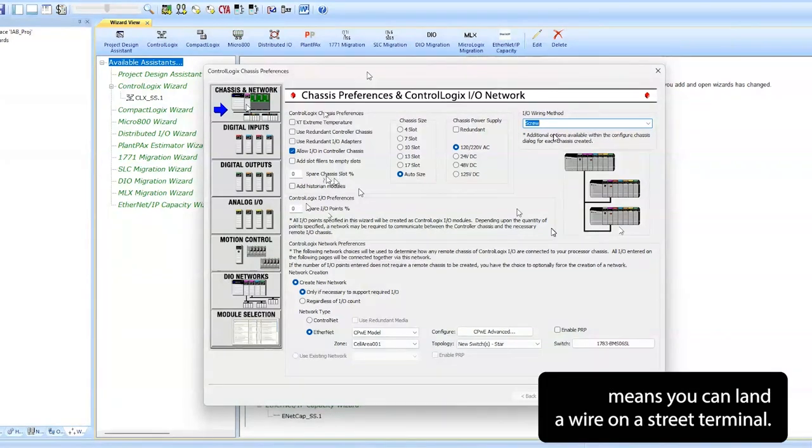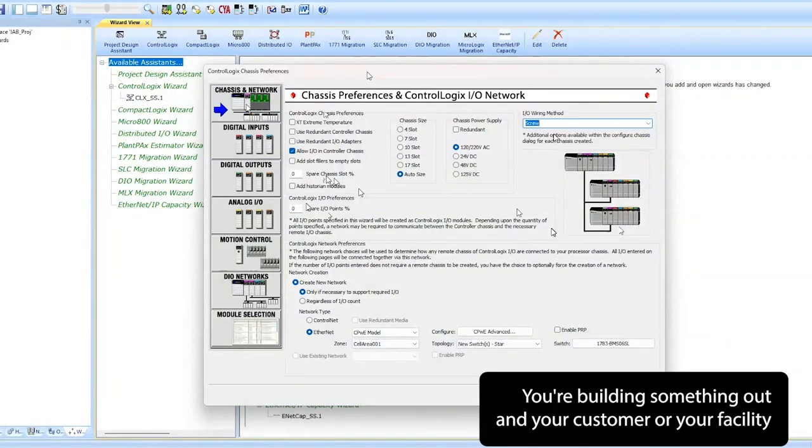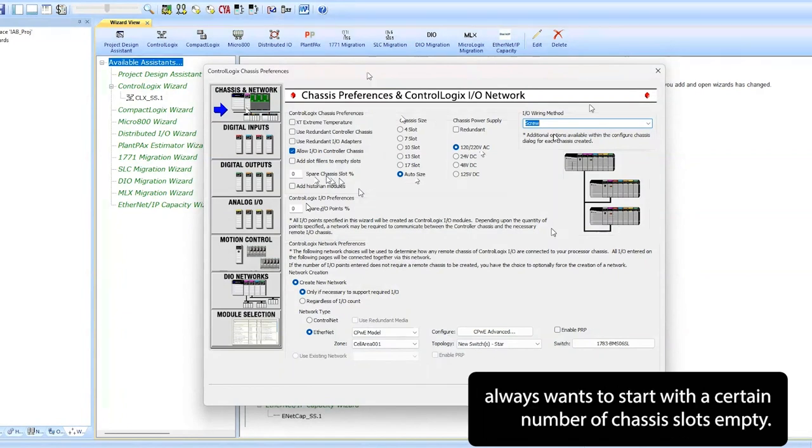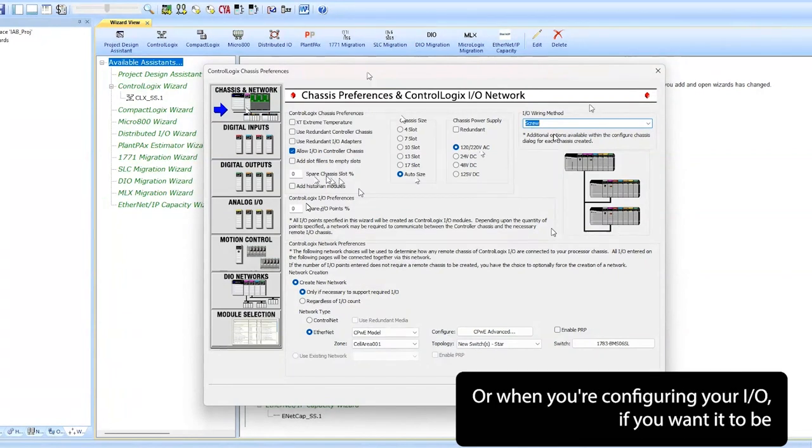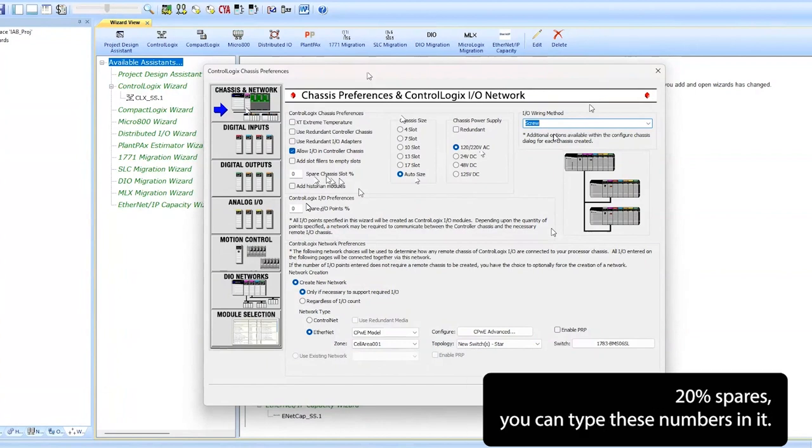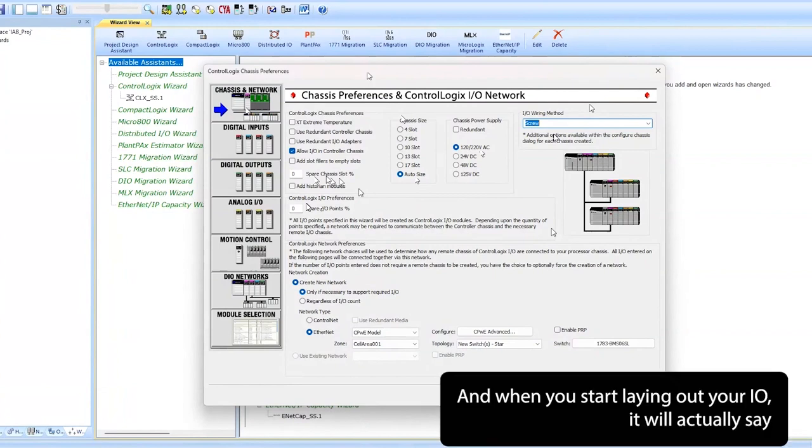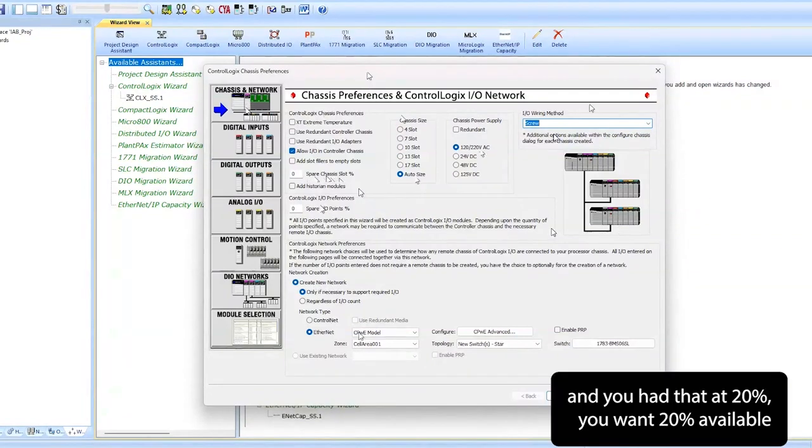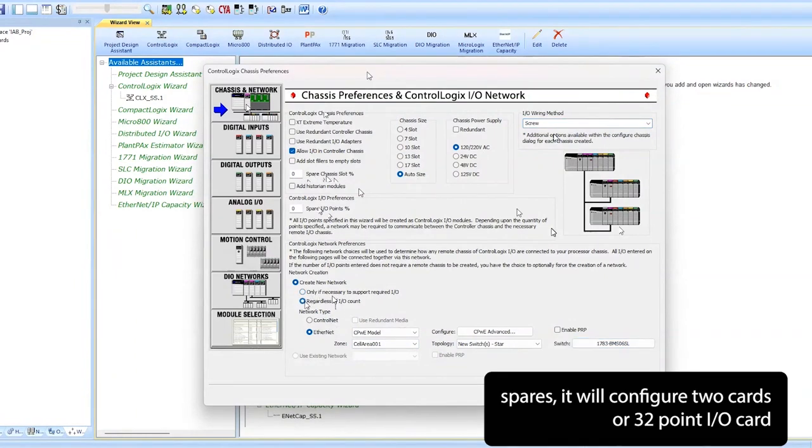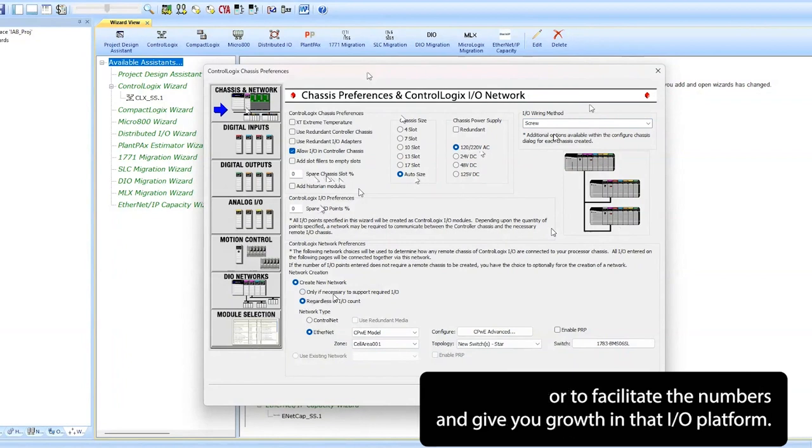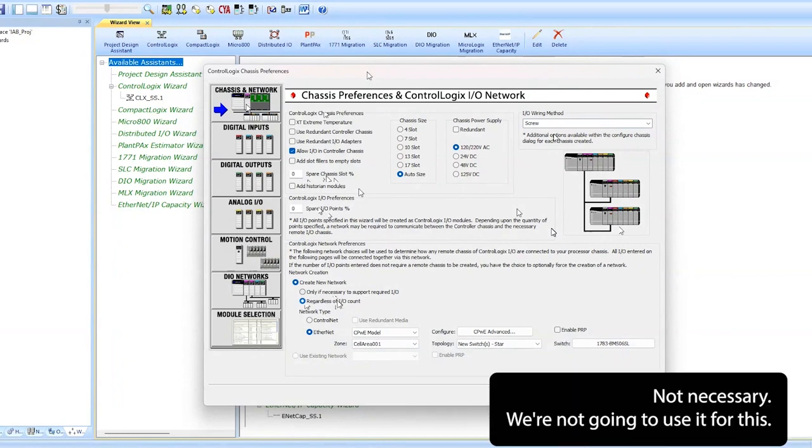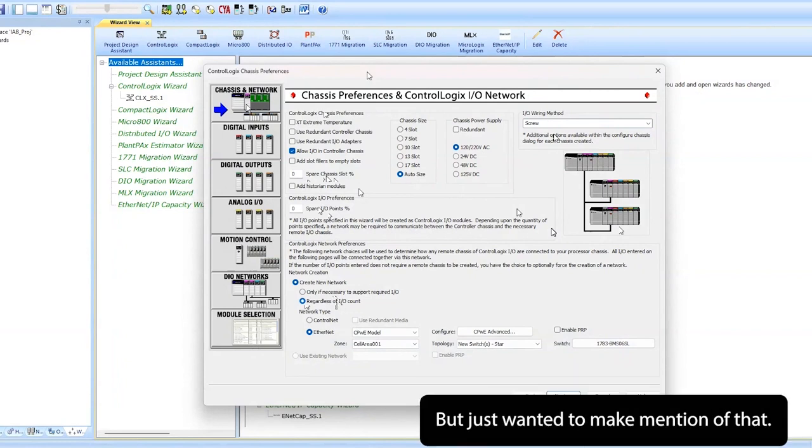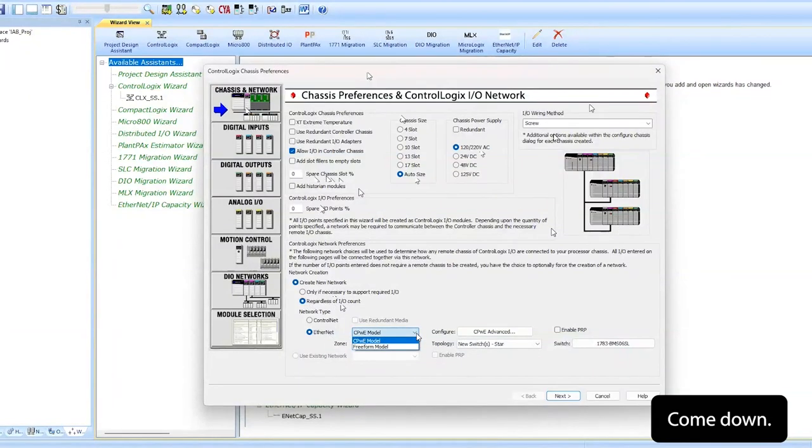If you're building something out and your customer or your facility always wants to start with a certain number of chassis slots empty, or when you're configuring your I/O, if you want it to be 20% spares, you can type these numbers in. When you start laying out your I/O, it will actually say if you needed 17 inputs and you had that at 20% spares, it will configure two cards or a 32-point I/O card to facilitate the numbers and give you growth in that I/O platform. Not necessary, we're not going to use it for this, but just wanted to make mention of that.